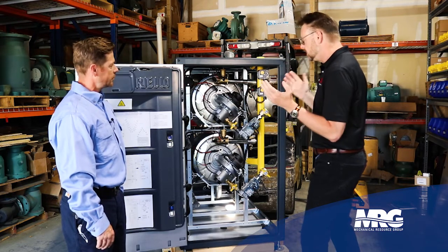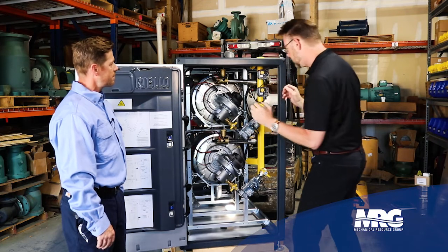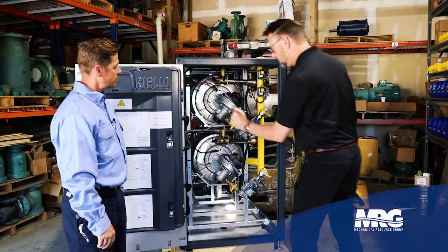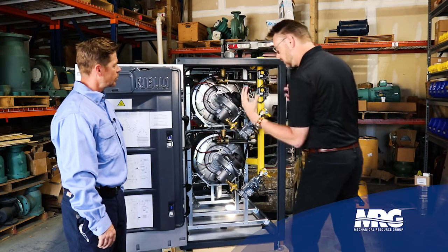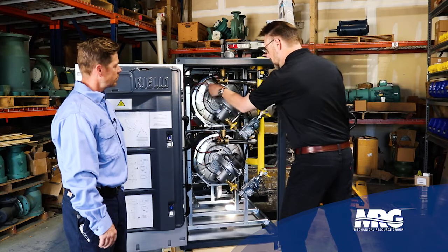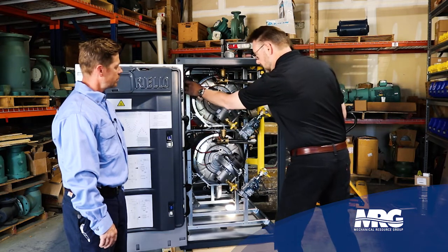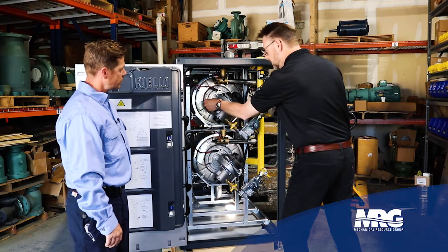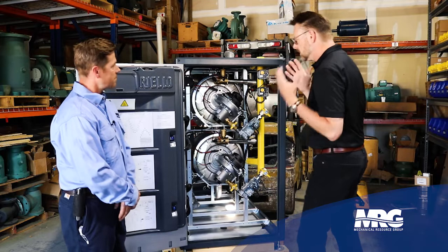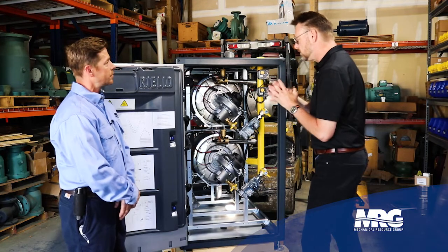Sure. Here, just real quick, we have gas entering the combustion system here. We need air that's coming through the cabinet, drawn by the blower, and then we're going to spark it with this device off of the ignition transformer, and we're going to prove that flame with this flame rod. Typically, where does that problem manifest?